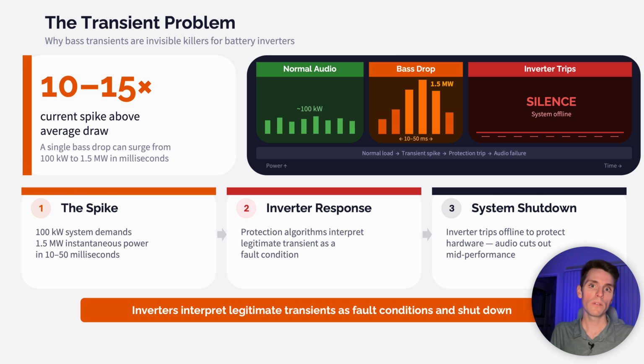But it gets worse. Electronic music in particular creates extreme transient loads. Bass drops produce current spikes 10 to 15 times above average, lasting 10 to 50 milliseconds. A 100 kilowatt audio system can demand 1.5 megawatts instantaneously. Inverter protection algorithms interpret these legitimate transients as fault conditions and completely shut down. The audio cuts out in the middle of the show.